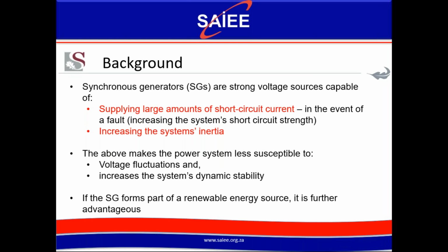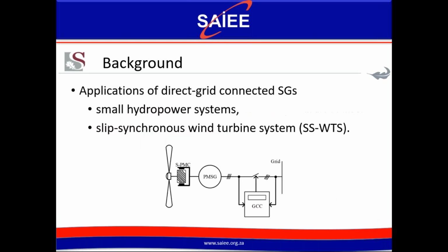Synchronous generators are strong voltage sources capable of supplying large amounts of short circuit current in the event of a grid fault. Consequently, connecting synchronous generators directly to microgrids has the advantage of increasing the system's inertia, while increasing the system's dynamic stability, while making the system less susceptible to voltage fluctuations. If the synchronous generator can form part of a renewable energy source, it is further advantageous. Two applications of direct grid connected synchronous generators include small hydropower systems and the slip synchronous wind turbine system, which is the focus of this paper.